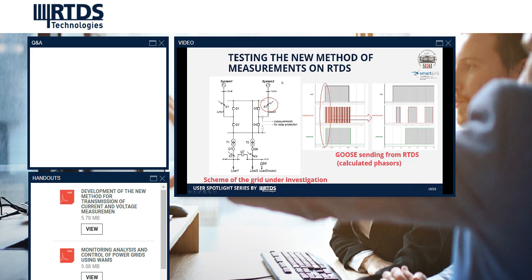Next, the newly calculated phasor values are periodically sent as GOOSE messages every 10 milliseconds. The GOOSE message generation occurs as long as the fault detector in the merging unit senses the presence of the fault.